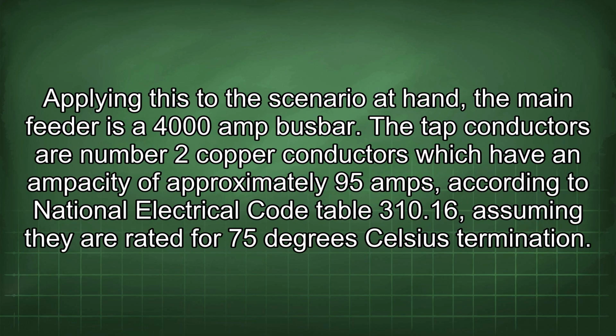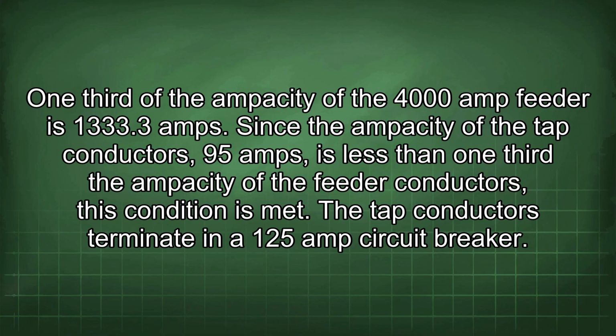Applying this to the scenario at hand, the main feeder is a 4000 amp bus bar. The tap conductors are number 2 copper conductors which have an ampacity of approximately 95 amps, according to National Electrical Code Table 310.16, assuming they are rated for 75 degrees Celsius termination. 1/3 of the ampacity of the 4000 amp feeder is 1333.3 amps. Since the ampacity of the tap conductors, 95 amps, is less than 1/3 the ampacity of the feeder conductors, this condition is met.